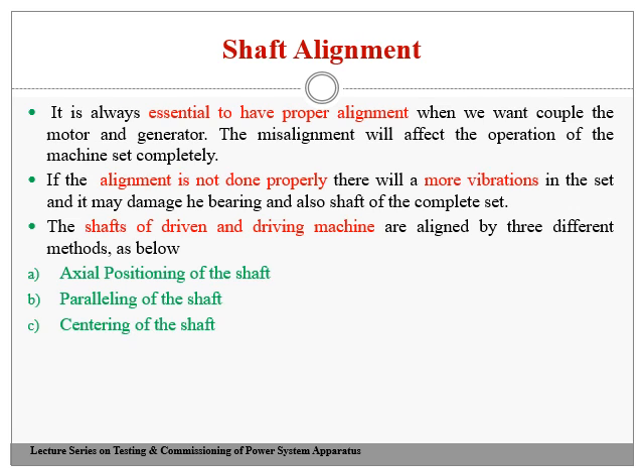Now we go to the shaft alignment. It is always essential to have proper alignment. Now let us see why shaft alignment is required. When the motor is existing alone, there is no need for shaft alignment. This comes into the picture whenever you are going to couple the induction motor to other equipment, like a drive, or a generator, maybe a DC generator or an AC generator. At that time, shaft alignment comes into the picture. This also helps in providing the proper air gap between the rotor and the stator of the induction motor.